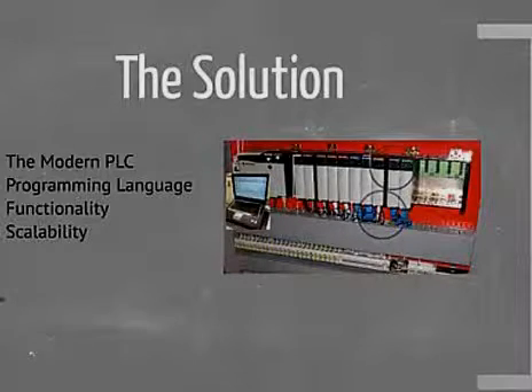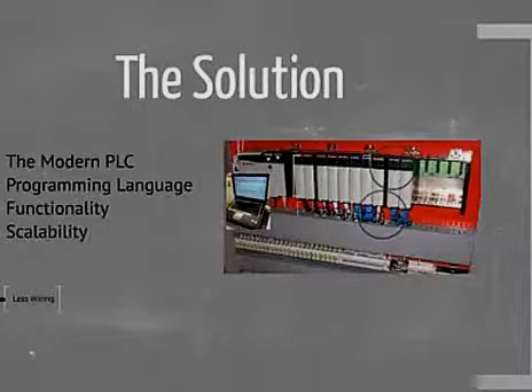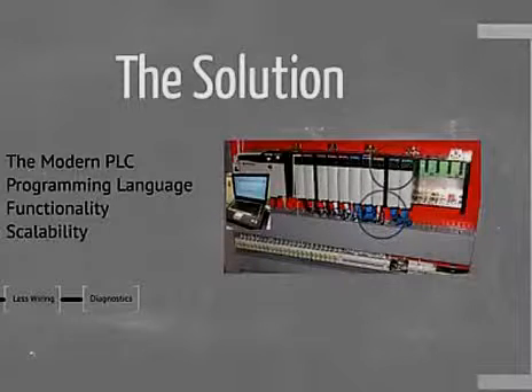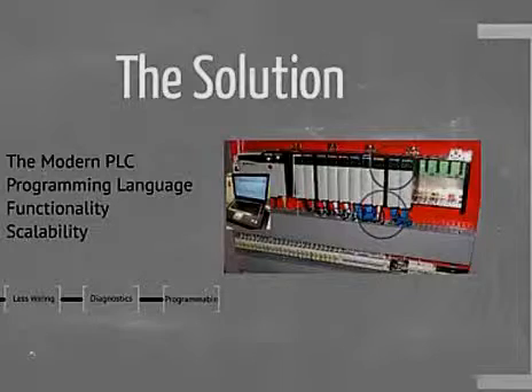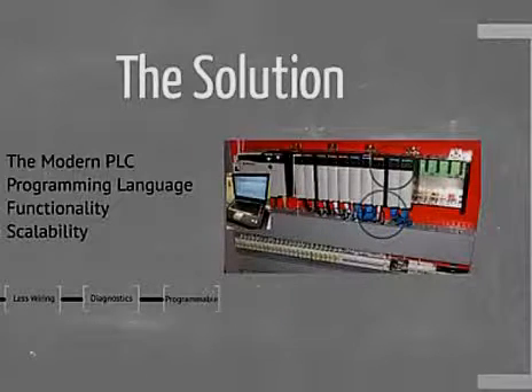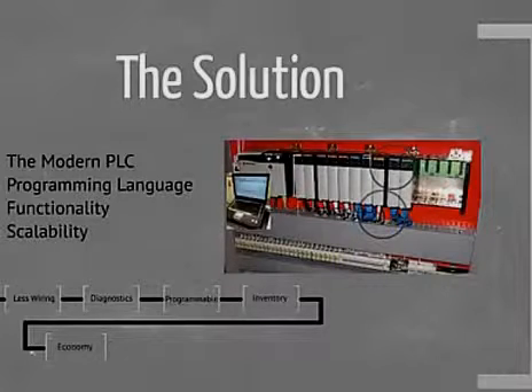The advantages of a control panel that is based on a PLC controller could be summed up in a few basic points. Number one, compared to a conventional process control system, the number of wires needed for connections is reduced by approximately 80%. Second, the diagnostic functions of a PLC controller allow for fast and easy error detection. Third, changes in operating sequence or application of a PLC controller to a different operating process can be easily accomplished by replacing the program through a console or using PC software, not requiring changes in wiring unless addition of some input or output device is required. Fourth, it requires fewer spare parts. Five, it is much cheaper compared to a conventional system, especially in cases where a large number of input and output instruments are needed and when operational functions are complex.